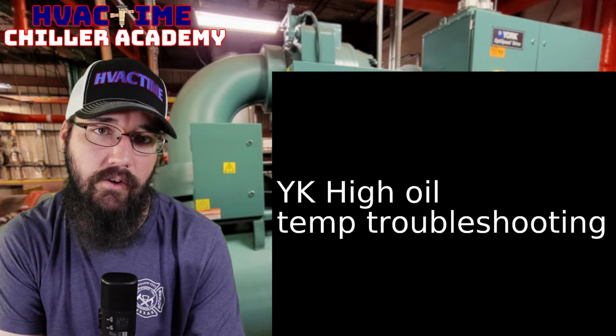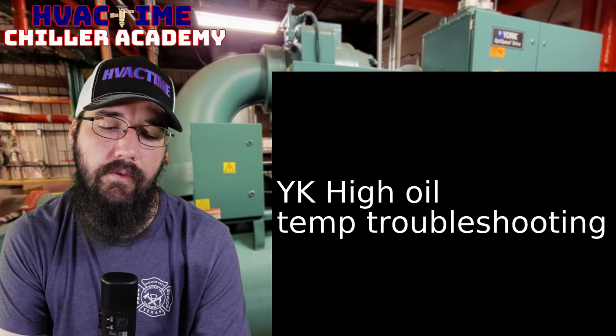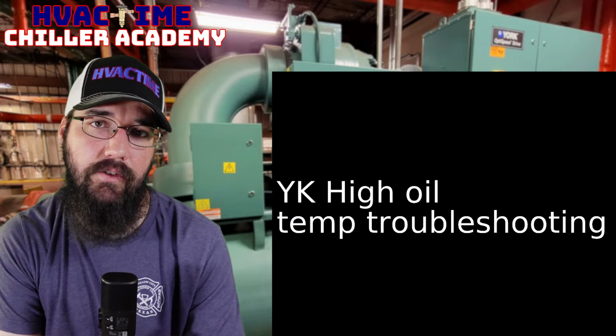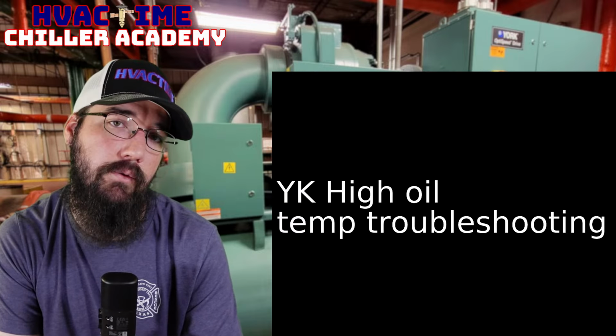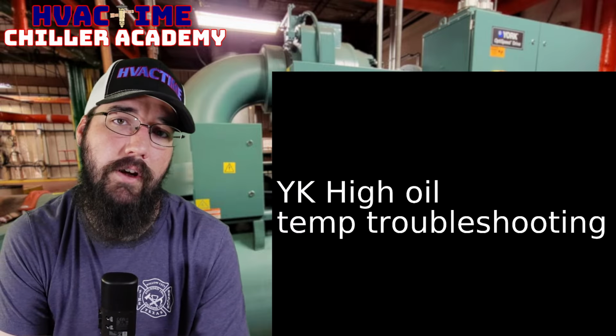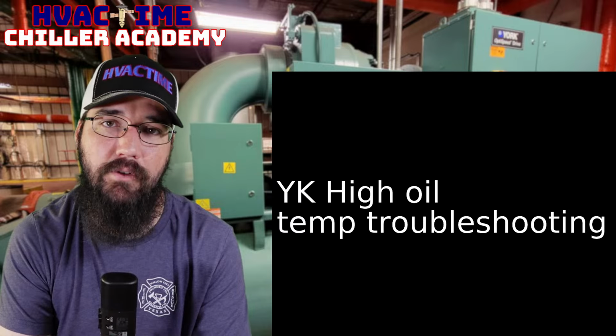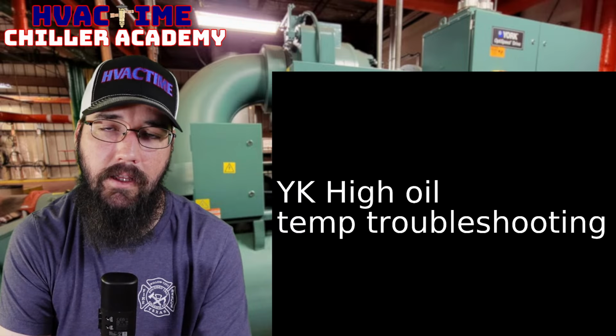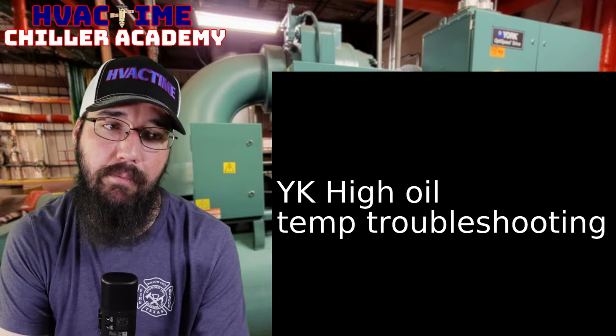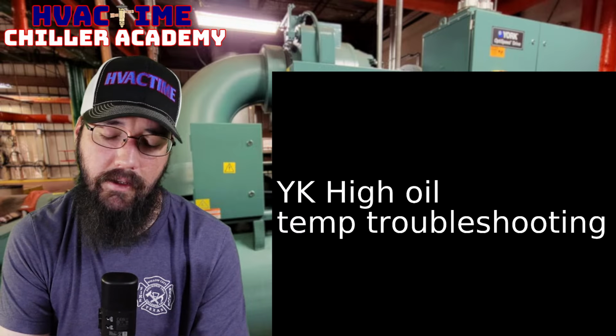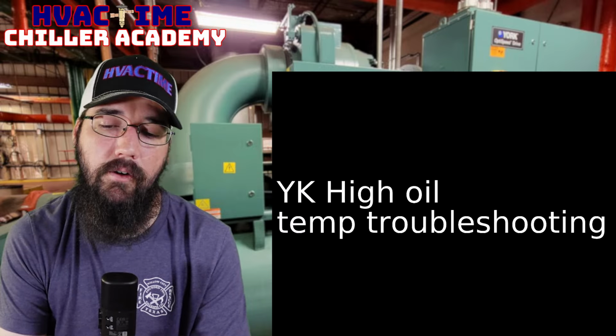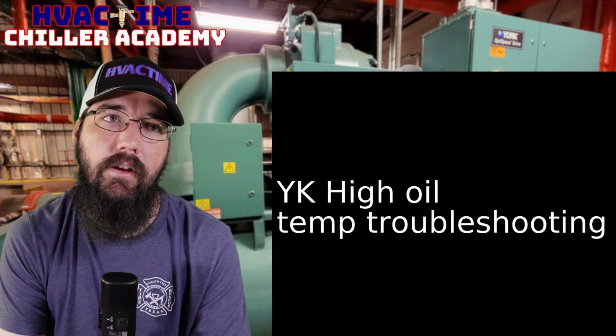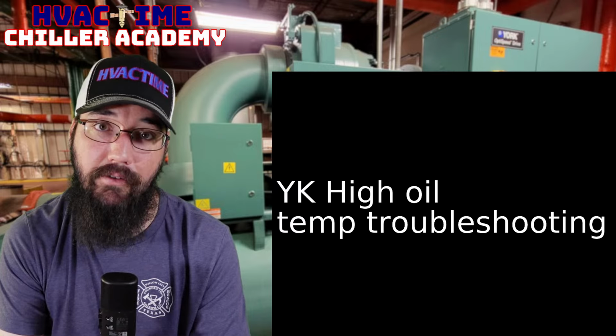It's not like these other machines where they have economizers and such to make up for it. So they're not trying to achieve subcooling, they're just trying to get to a full liquid state. With a YK, we have a dedicated subcooler circuit. We need that machine to have subcooling in order to function, not only at the evaporator and the metering device correctly, but also at our oil cooler metering valve.